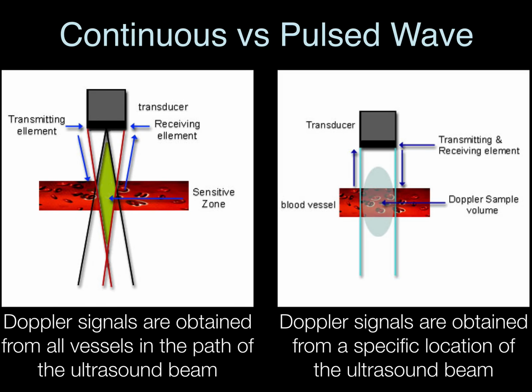Now that's pulse wave Doppler. Pulse wave Doppler right here, that's what we did. We did a very specific sampling location. Now the problem with that is if you've got an area that's really stenotic, and maybe a small portion of the red blood cells are going really crazy high velocities, if you don't have your pulse wave Doppler sampling gate in the exact right spot, you might miss the highest velocities. You're only going to get what you're sampling in a very specific area.